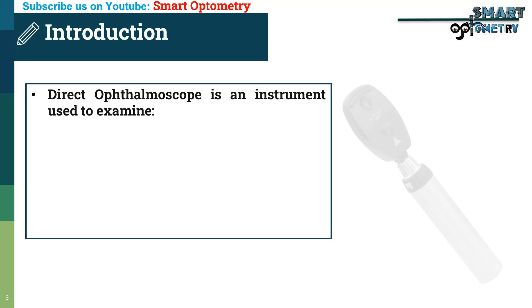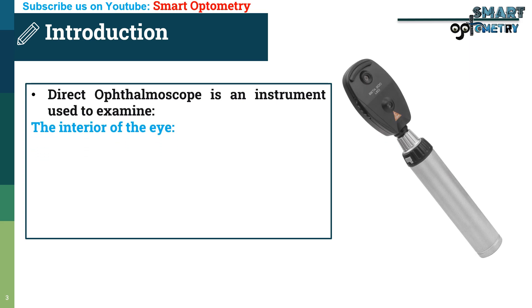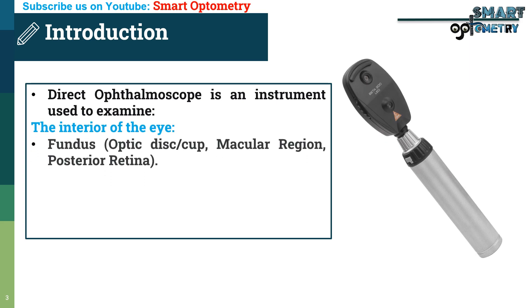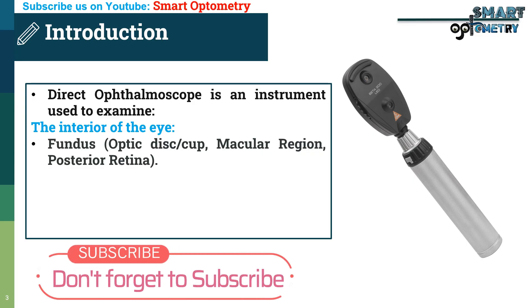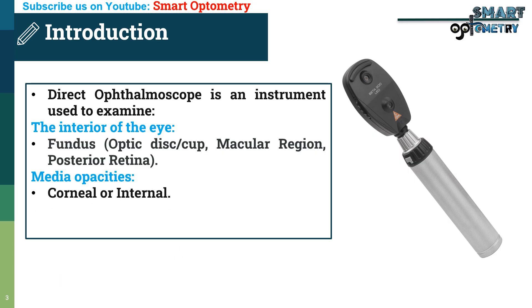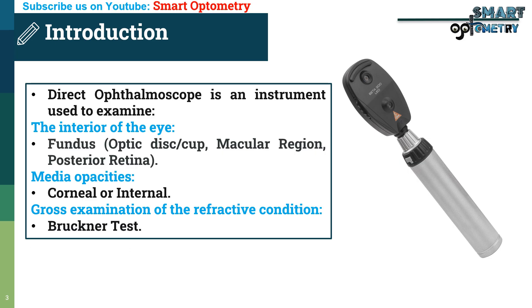The direct ophthalmoscope is an instrument used to examine the interior of the eye, i.e. the fundus, which includes the optic disc, optic cup, macular region, and part of the posterior retina. It also allows examination of media opacities — we can identify corneal or internal opacities. Additionally, gross examination of refractive condition is possible; we can perform the Bruckner test, which gives a rough estimation of the refractive status of the eye.